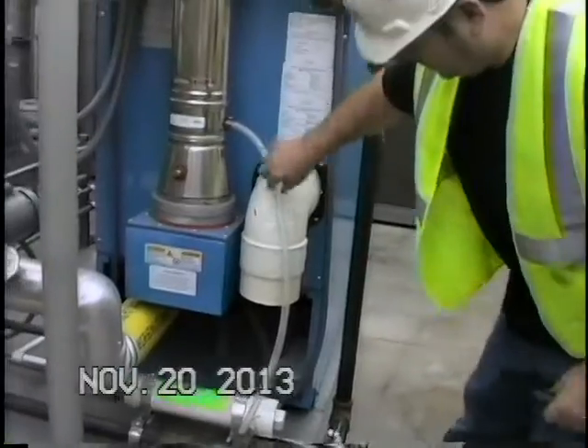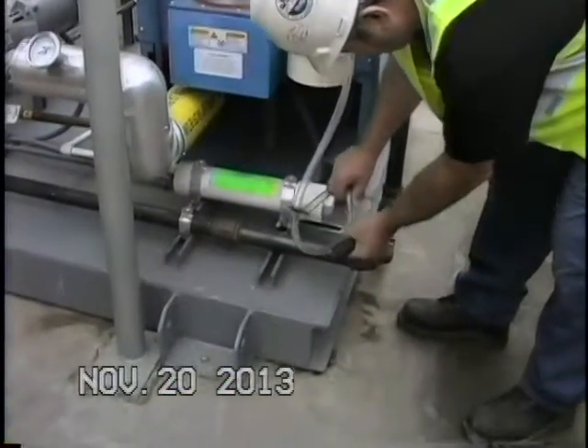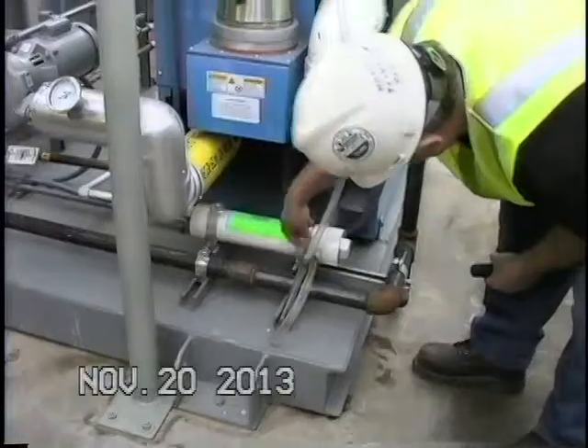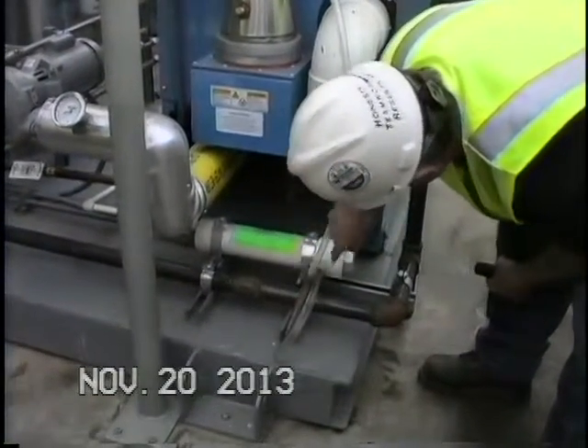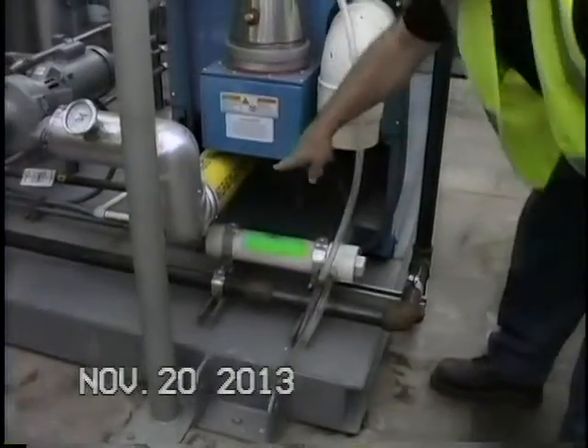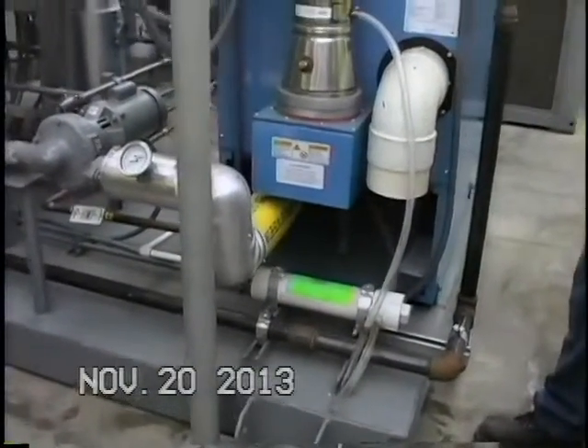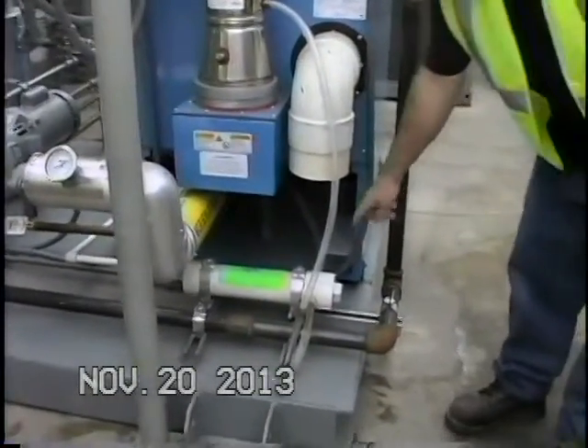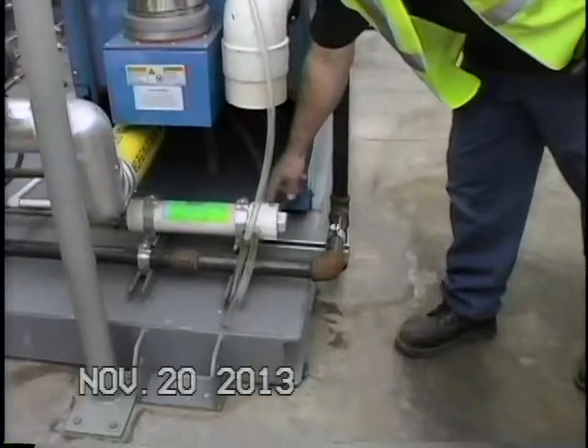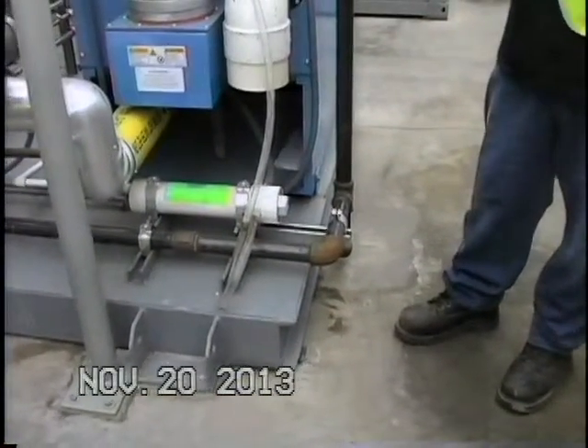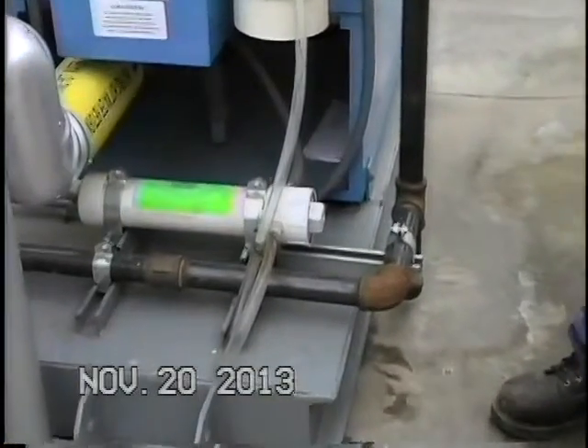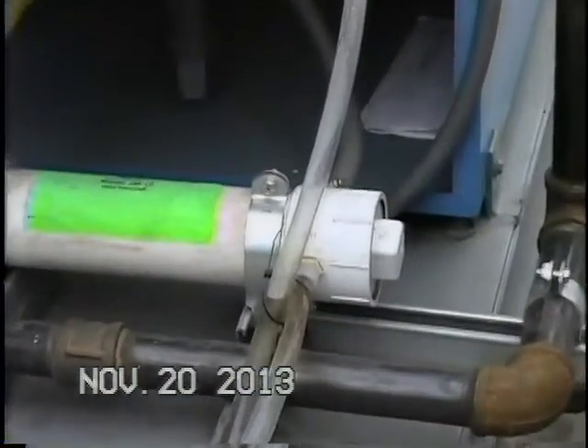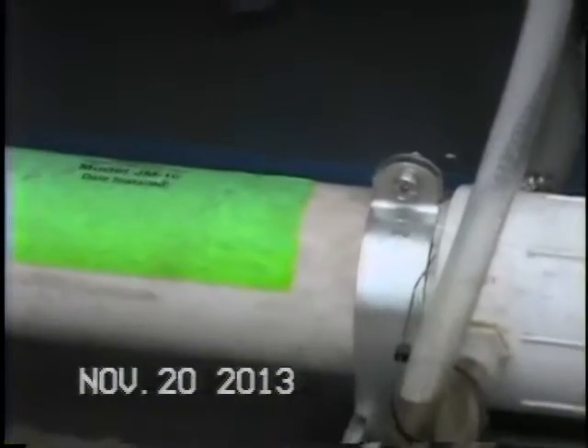Okay, here is your condensate line from the flue. It's dripping down here. Here's your air trap. It's going into this little neutralizer and then going out to the drain. It makes it safe so it doesn't eat up your drains. This is on your list. I think once a year you pull the end apart and you check to make sure that the limestone isn't all gone. You know what I mean? You want to check that. So once every 6 months, you look in there, depending on how much condensate you're running through there.